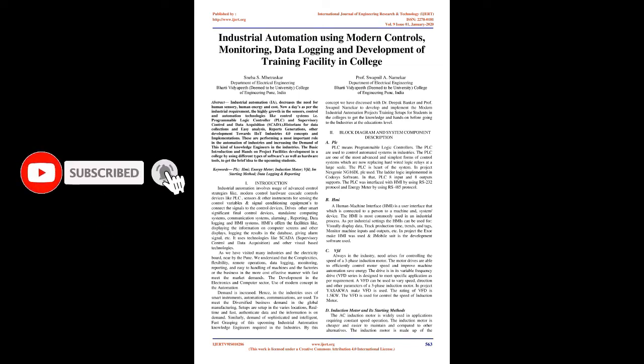Introduction. Industrial automation involves usage of advanced control strategies like modern control hardware, cascade controls, devices like PLC, sensors and other instruments for sensing the control variables, and signal conditioning equipment to connect the signals to the control devices, drives, and other smart, significant final control devices, standalone computing systems, communication systems, alarming, reporting, data logging and HMI systems. HMIs offer facilities like displaying information on computer screens and other displays, logging the results in the database, giving alarm signals, etc. It uses technologies like SCADA, supervisory control and data acquisition, and other visual-based technologies.